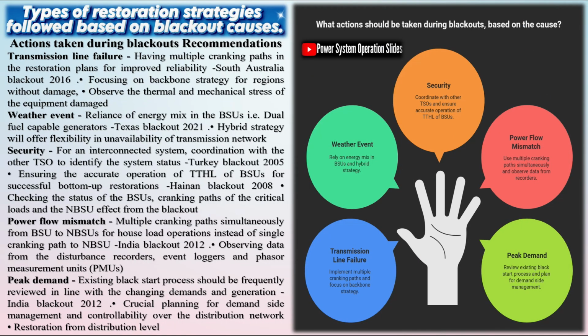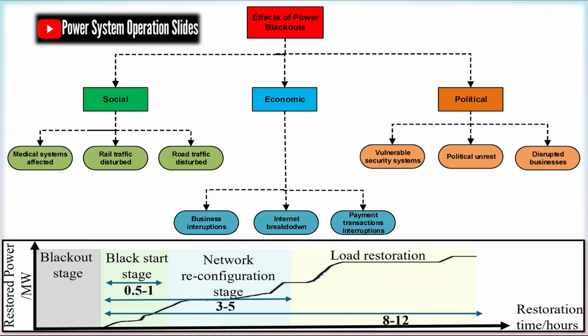These prioritize stabilizing the grid, energizing key transmission corridors, and gradually bringing generation units and customer loads back online. Success hinges on thorough preparedness. This includes operator training, clear procedural documentation, robust communication systems, verified black start capabilities, and reliable cranking paths. Power systems operate within defined boundaries and can shift between several recognized states depending on system conditions and constraints. These states reflect the system's stability, security, and ability to respond to unexpected events. While the exact definitions may vary by region or regulatory body, the general framework remains consistent.